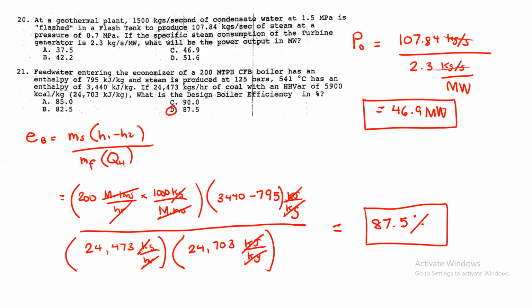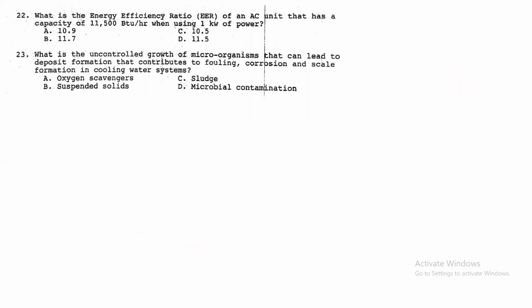So next. So 22. What is the energy efficiency ratio of an AC unit that has a capacity of 11,500 BTU per hour when using 1 kilowatt of power? So paano to guys? So when using 1 kilowatt of power.